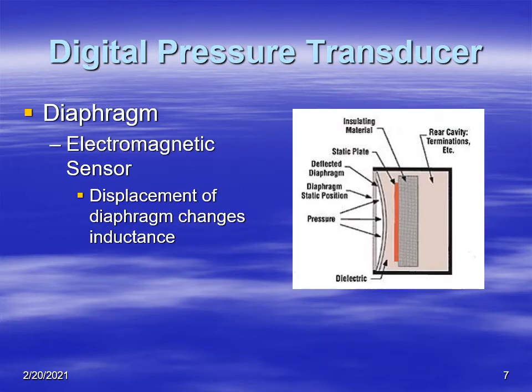Another type of diaphragm is one that uses an electromagnetic sensor. Once again, you have a diaphragm and an evacuated chamber, very much like the capacitance type sensor. As the membrane flexes, instead of getting changes in capacitance, you get changes in inductance. So it uses a slightly different electrical property.